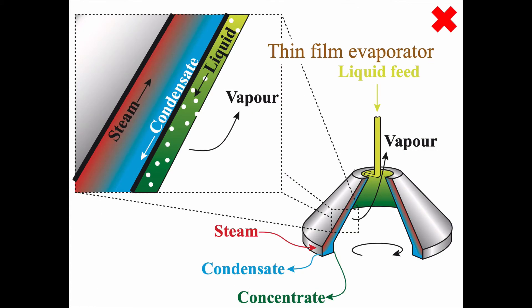A thin film evaporator is like an Alfa Laval separator — you have a spinning element and the liquid is poured in on the inside. The liquid flows down in a thin film; it's a two-wall construction with an inside and an outside. Steam is let in on the inside, condenses on the surface, and releases heat to the liquid, causing it to boil. You collect the vapor here and the condensate flows out here.